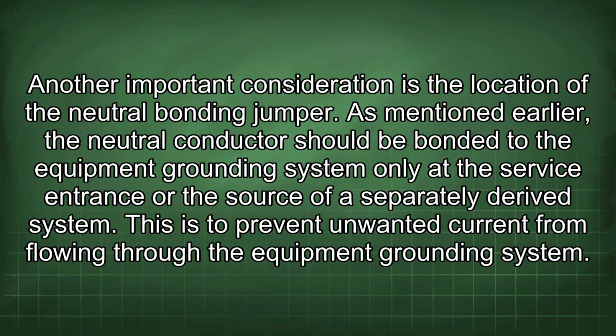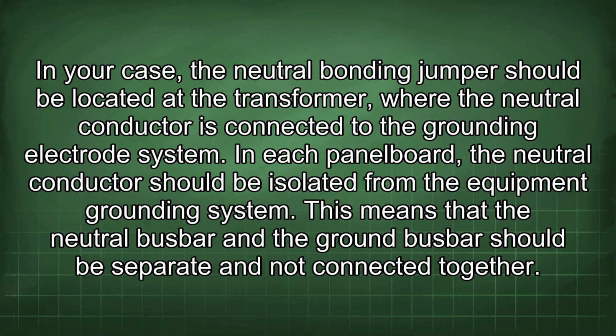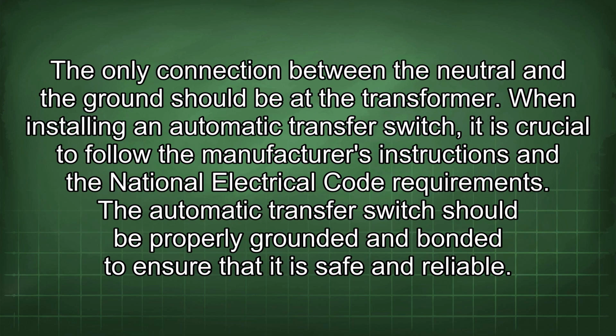Another important consideration is the location of the neutral bonding jumper. As mentioned earlier, the neutral conductor should be bonded to the equipment grounding system only at the service entrance or the source of a separately derived system. This is to prevent unwanted current from flowing through the equipment grounding system. In your case, the neutral bonding jumper should be located at the transformer, where the neutral conductor is connected to the grounding electrode system. In each panel board, the neutral conductor should be isolated from the equipment grounding system. This means that the neutral busbar and the ground busbar should be separate and not connected together. The only connection between the neutral and the ground should be at the transformer.